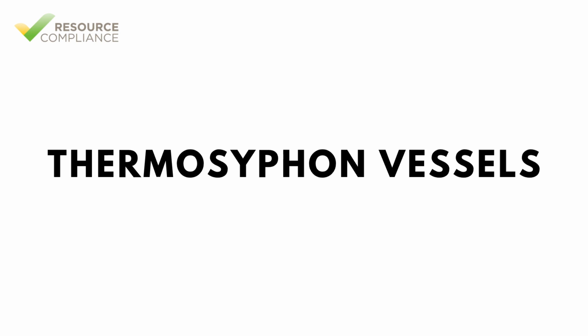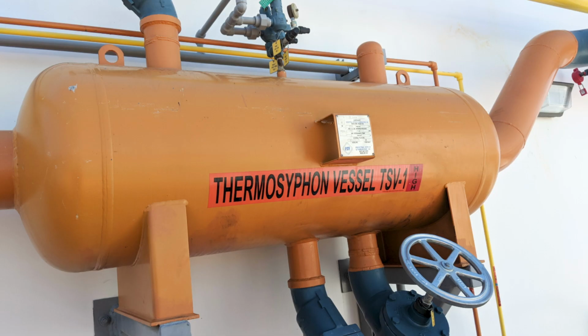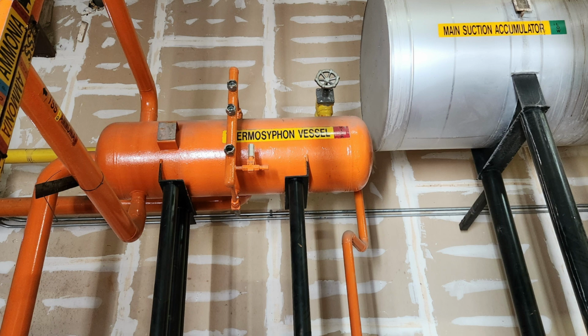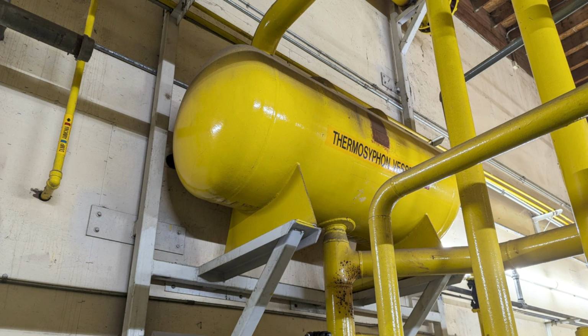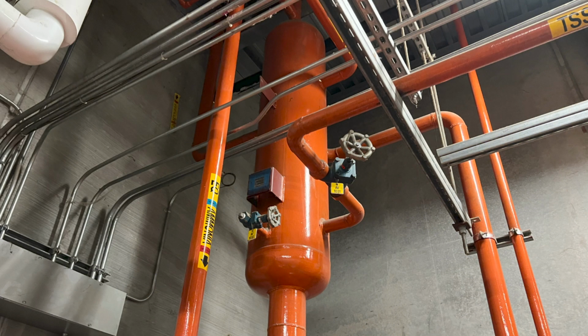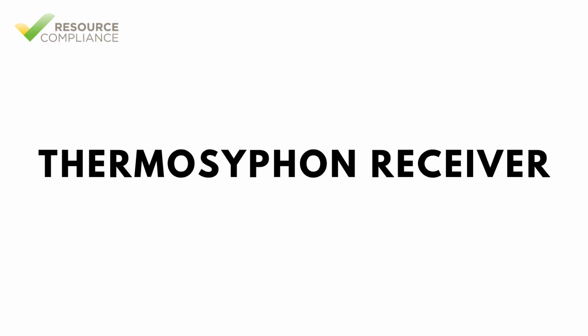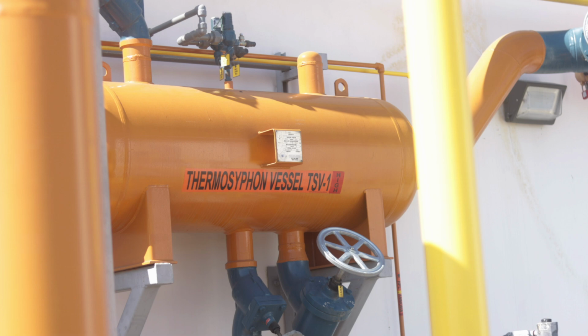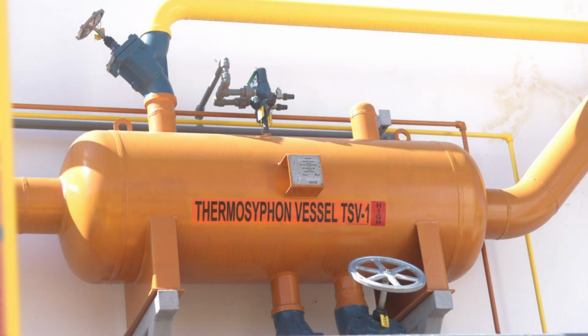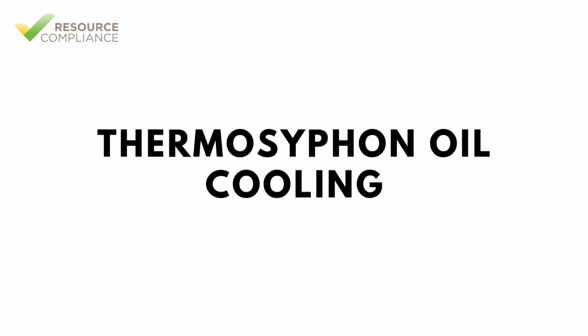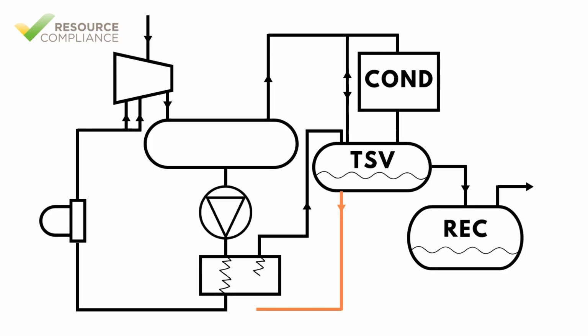A thermosyphon vessel is a specialized vessel used to circulate refrigerant between a condenser and a compressor oil cooler using gravity and natural convection without a mechanical pump. Sometimes referred to as a thermosyphon receiver, these vessels are only employed in systems where the compressors are cooled by thermosyphon oil cooling. Thermosyphon oil cooling is accomplished by supplying saturated liquid ammonia at the condensing pressure to an external heat exchanger mounted adjacent to a screw compressor. This liquid is supplied from the thermosyphon vessel.